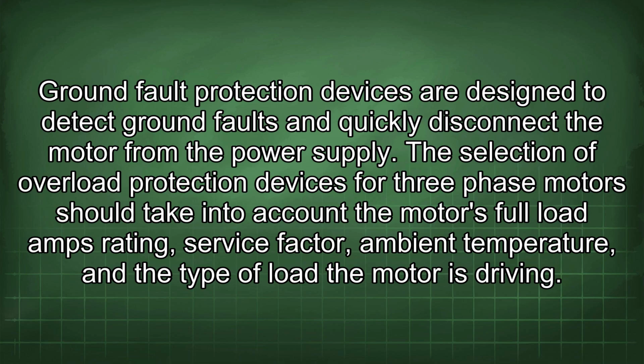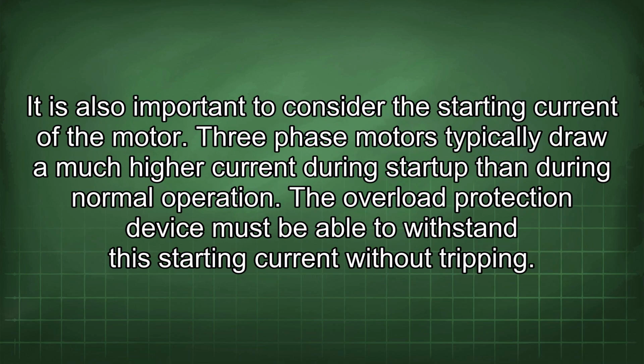The selection of overload protection devices for three-phase motors should take into account the motor's full load amps rating, service factor, ambient temperature, and the type of load the motor is driving. It is also important to consider the starting current of the motor. Three-phase motors typically draw a much higher current during startup than during normal operation. The overload protection device must be able to withstand this starting current without tripping.